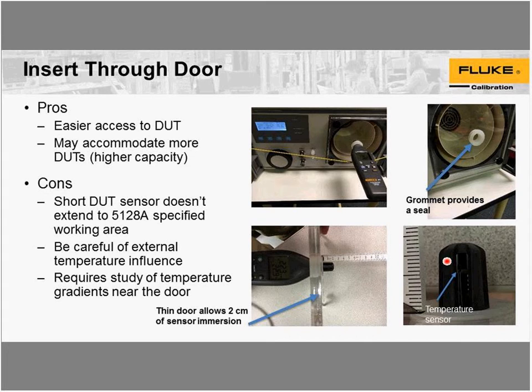The advantage here is, if I wanted to calibrate more than one unit at a time, I could drill more holes and install more grommets and mount more of them on the door like that.